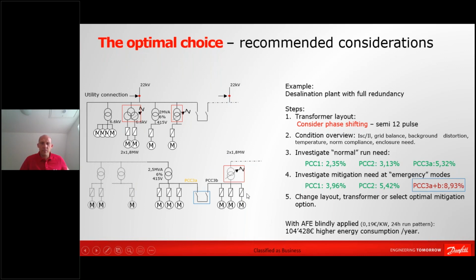Then, as said, what you need to do as a second step after you have considered this is actually to do investigations under normal operation mode. So what happens if it's running fed from two transformers separated in the middle? And in this specific case, I actually calculated the different PCC levels, so PCC1, PCC2, PCC3, and so forth. And I found out that there were no areas where I had very high voltage distortion. And that means actually that under normal running conditions, I don't need to do mitigation. There is no need for adding harmonic mitigation if I'm running at a normal loading condition.